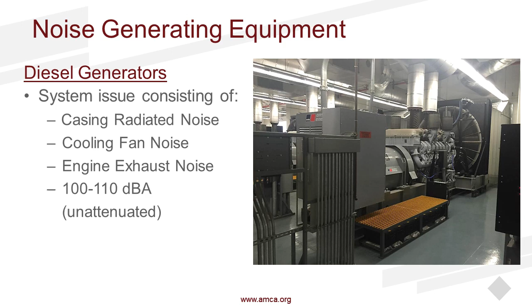These generator rooms are great — you walk in there, you want some muffs. It might be running 100 to 110 dBA within that space. So maintenance goes in wearing the muffs, that's great. But there's noise that breaks out of that room. You've got the fresh air intake noise and the discharge, say off a radiator. The noise within that room bounces around and becomes worse, and there may be multiple units running at a time, maybe 6, 7, 8, 10 generators working at once, or some mix of that. That noise is going to break out to the community.